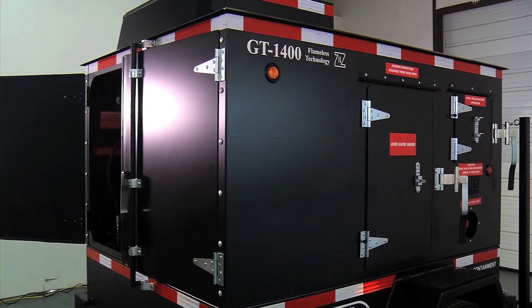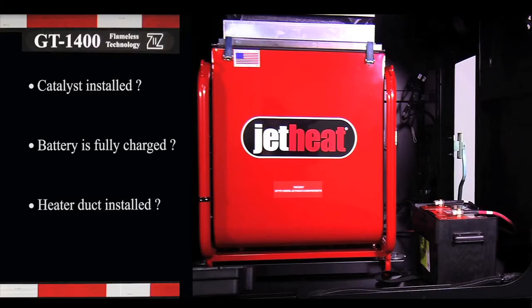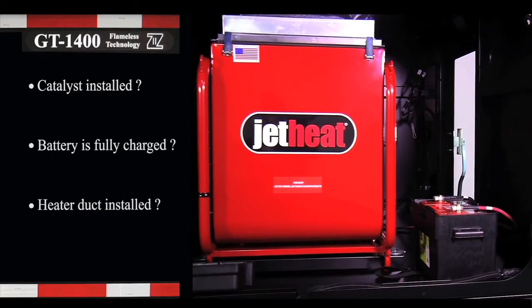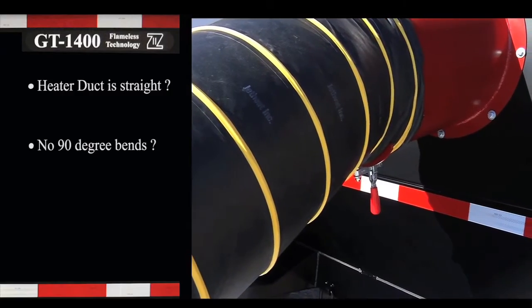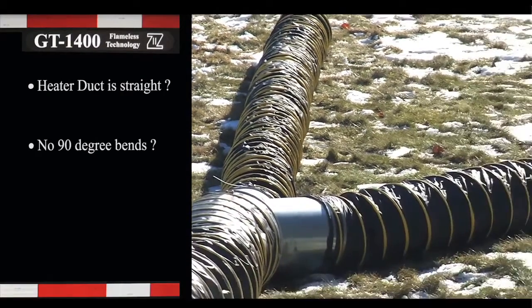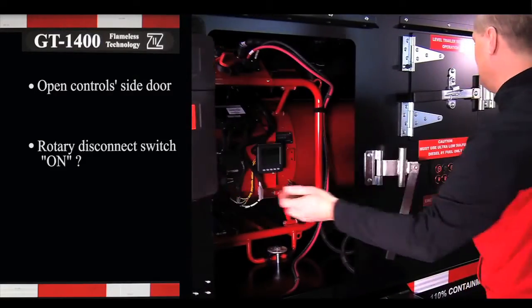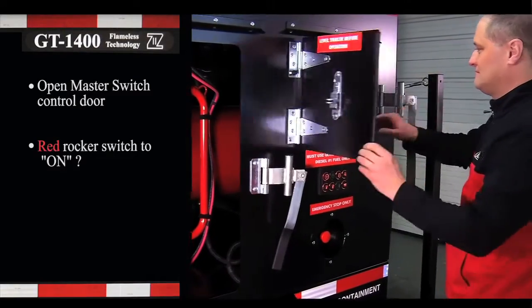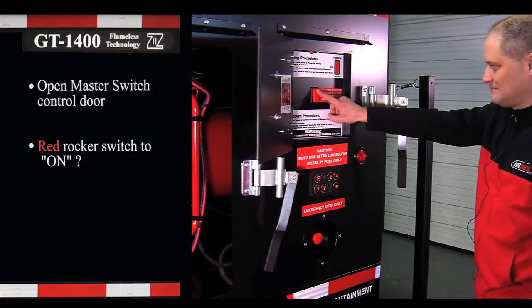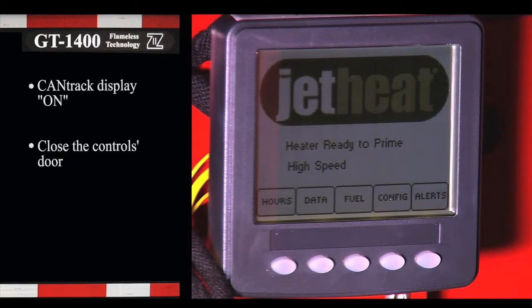Now let's look at how easy it is to start and manage heat from the powerful and efficient GT1400. First, ensure the catalyst is installed, the battery is fully charged, and a heater duct is installed. Be certain the heater duct is as straight as possible without any 90-degree bends. Open the control side door and check that the rotary disconnect switch is ON. Open the master switch control door, push the red rocker switch to ON, and check that the CANtrack display comes ON, then close the controls door.